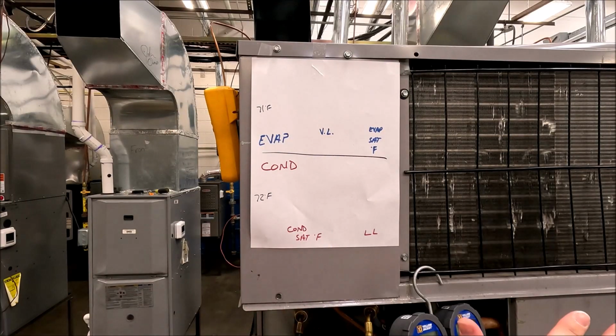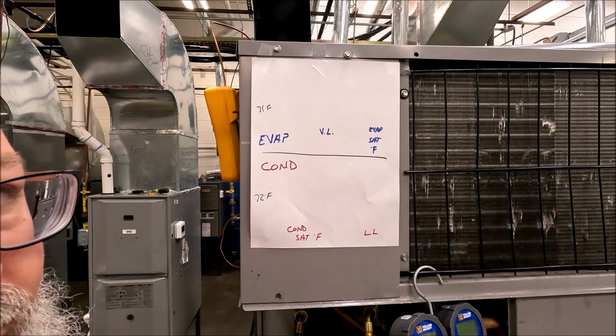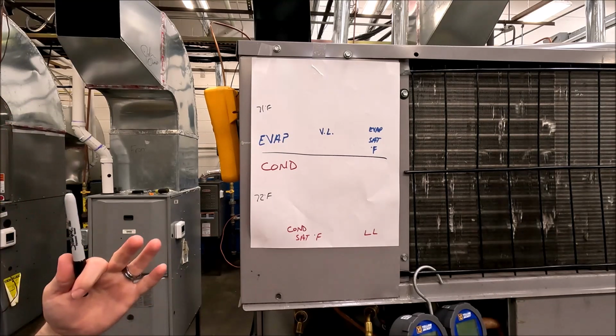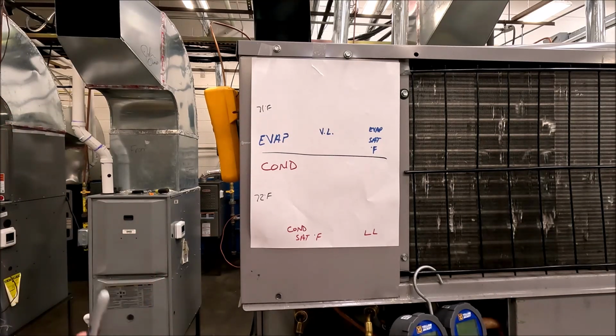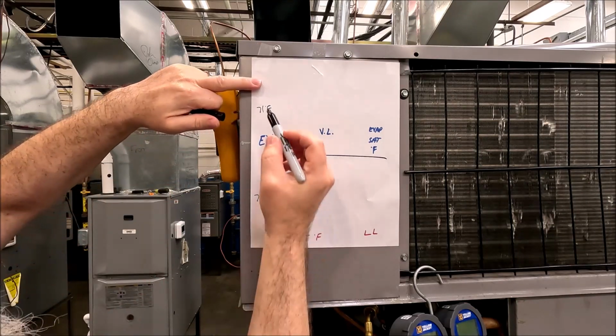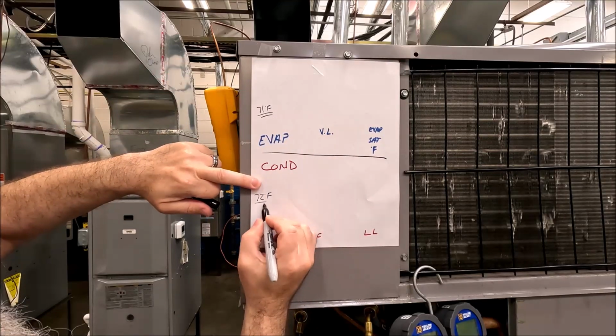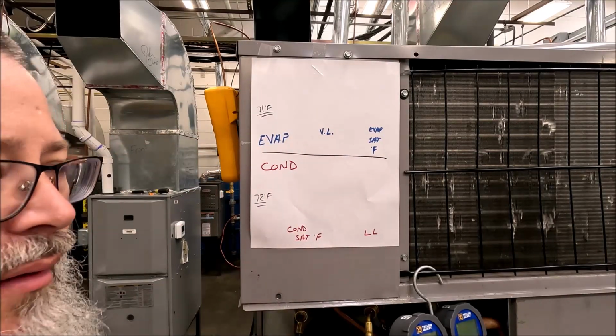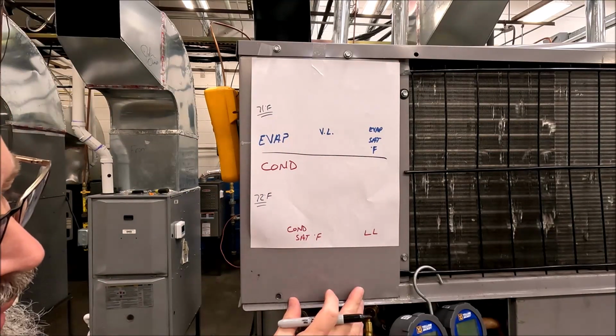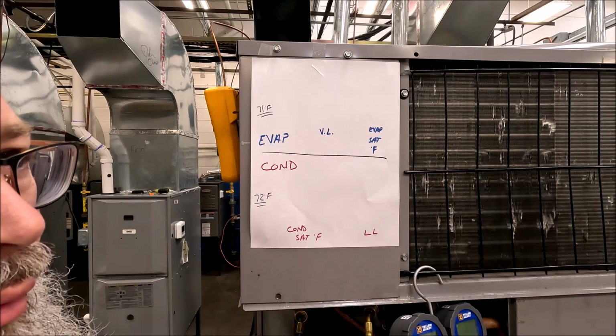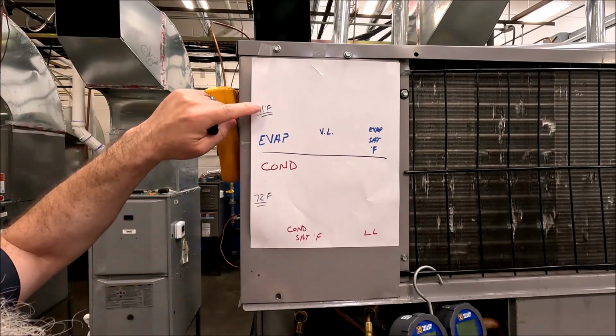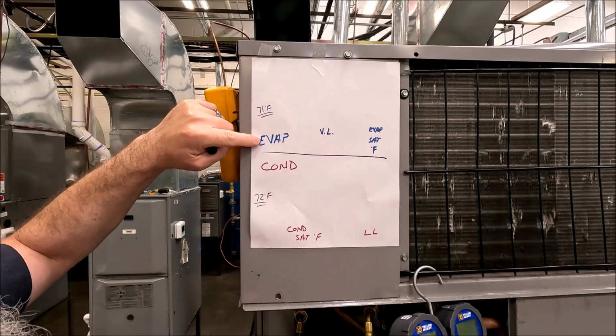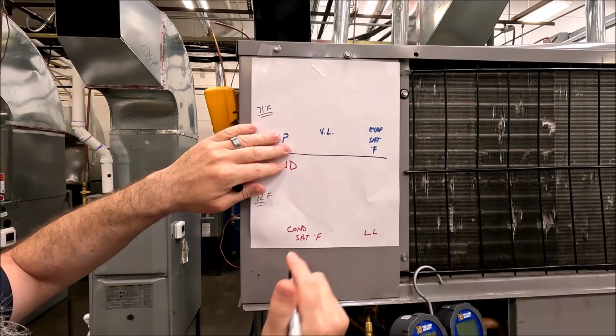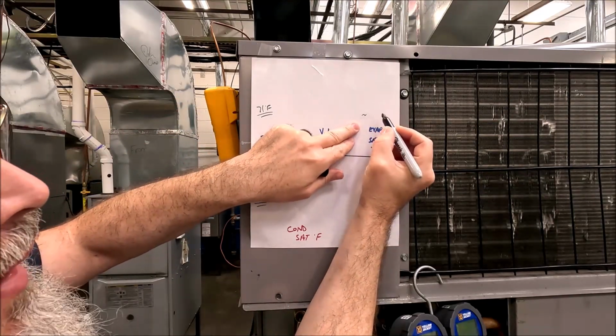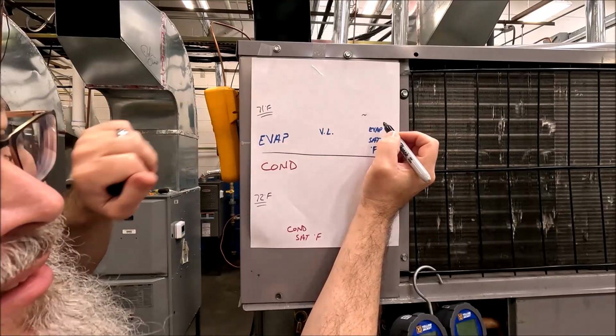So I'm not looking at the gauges yet. Matter of fact, they've timed themselves off. But if we ran through just real quick without breaking out a true whiteboard, this number right here is going to help me estimate what I should get. Now I'm running a 410 system, and for numbers that I use, I know that my evaporator temperature should be about 30 degrees less than that.